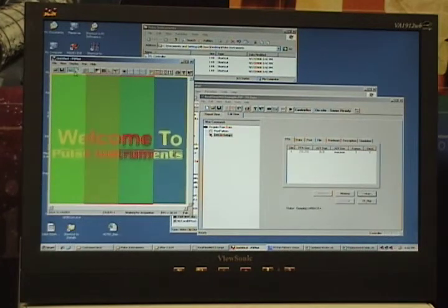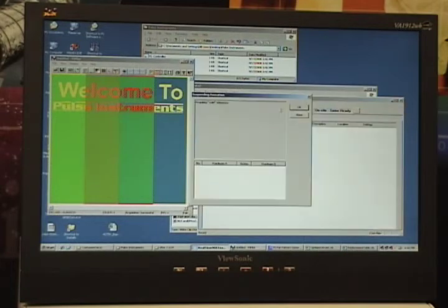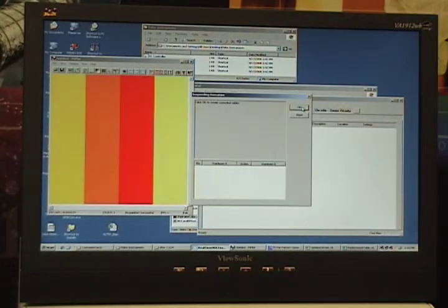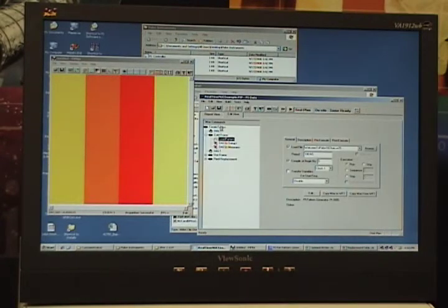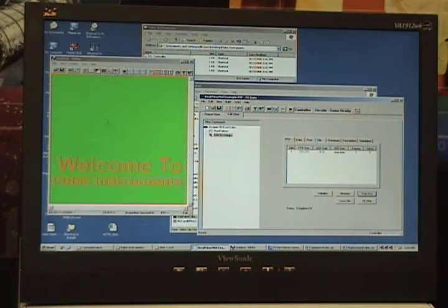I have a test plan to collect 32 frames of cold reference, 32 frames of hot reference, and also to read in a dummy bad pixel table. Once my tables have been created, I can then apply the 2-point NUC in real time, and the image now looks uniform. I can also apply bad pixel correction, although in this sample pattern there are no bad pixels to correct.